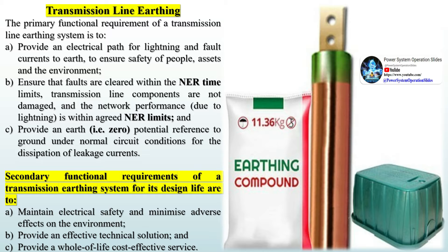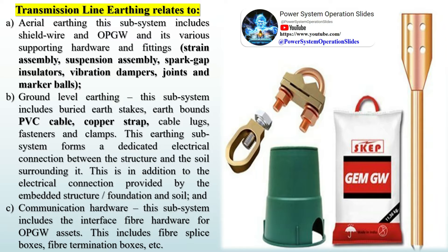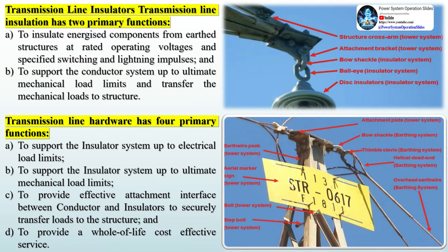Provide an earth zero potential reference to ground. Secondary functional requirements of a transmission earthing system are to maintain electrical safety, minimize adverse effects on the environment, and provide an effective technical solution. Transmission line earthing relates to aerial earthing. This subsystem includes shield wire and OPGW with various supporting hardware and fittings, strain assembly, suspension assembly, spark gap insulators, vibration dampers, joints, and marker balls. Ground-level earthing includes buried earth stakes, earth-bonded PVC cable, copper strap, cable lugs, fasteners, and clamps. Communication hardware includes interface fiber hardware for OPGW assets, such as fiber splice boxes and fiber termination boxes.